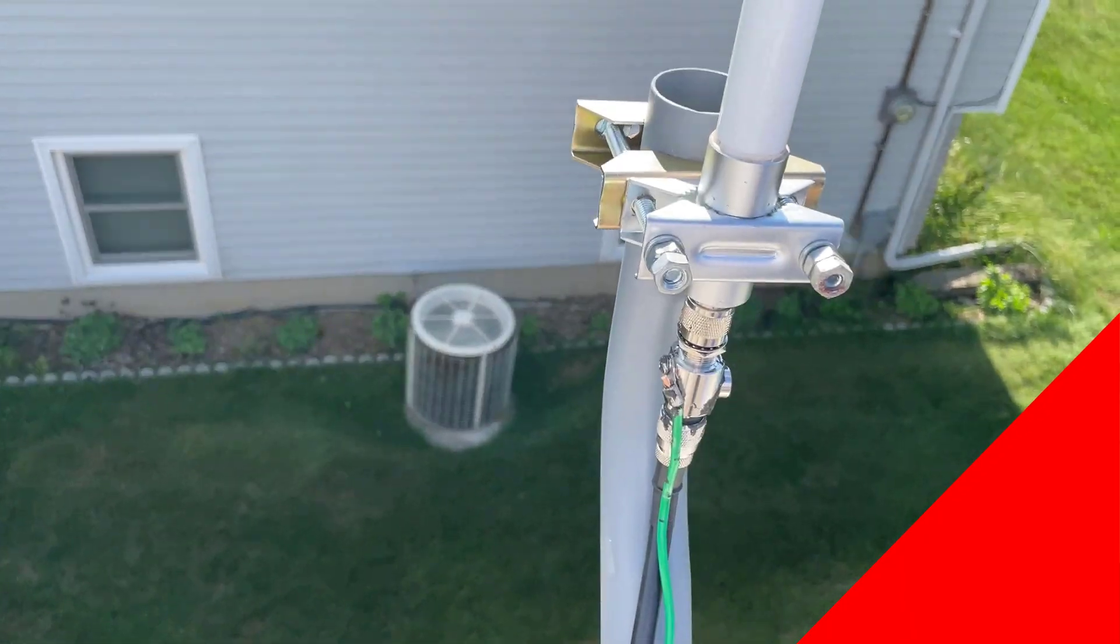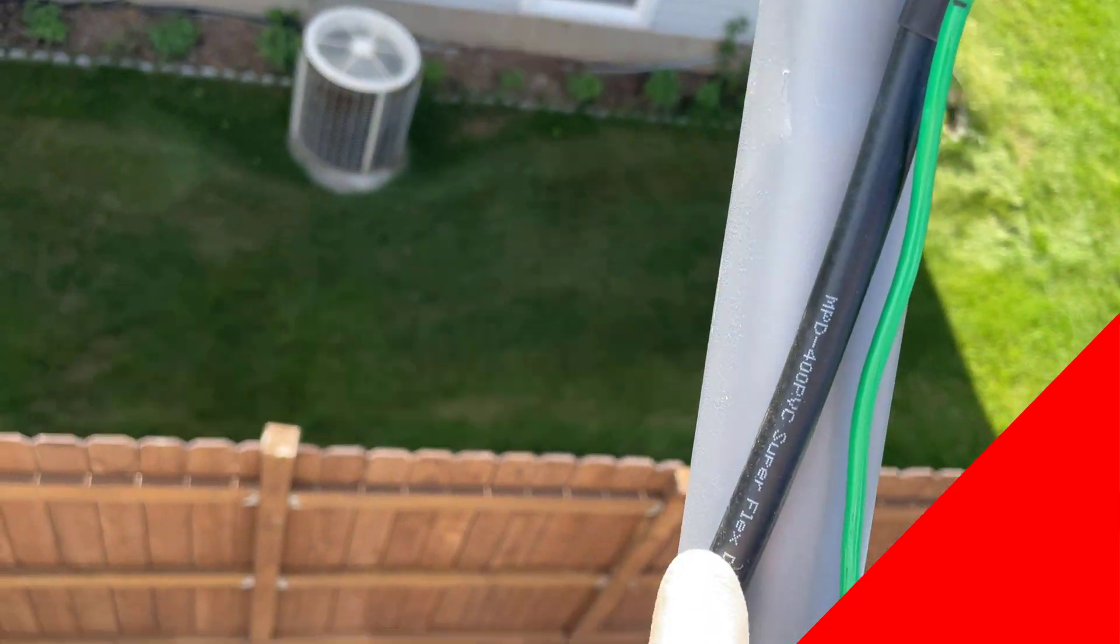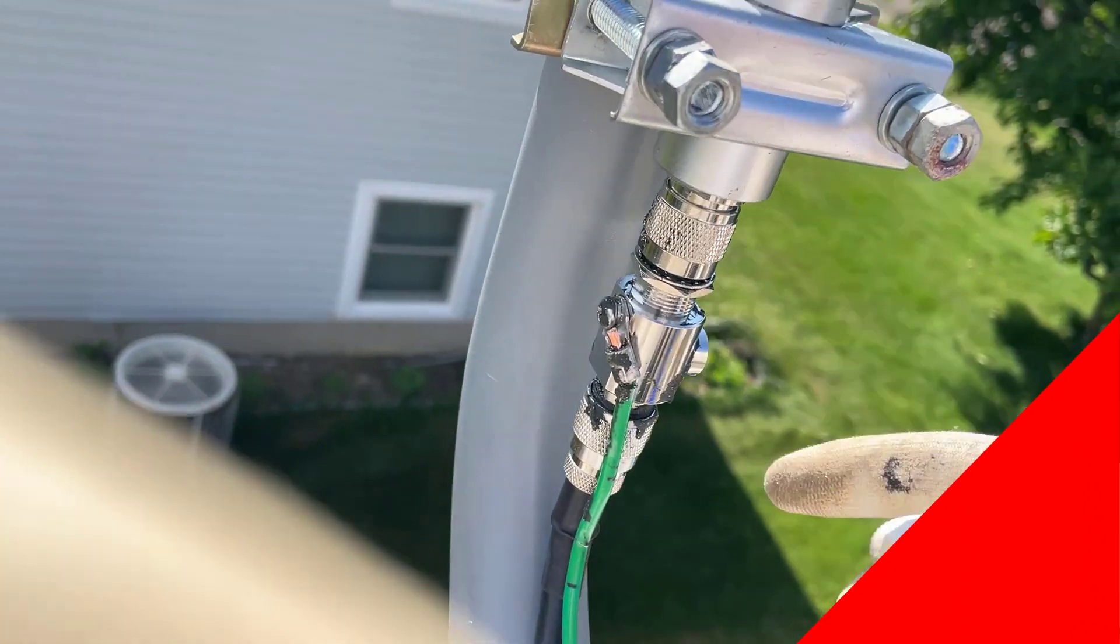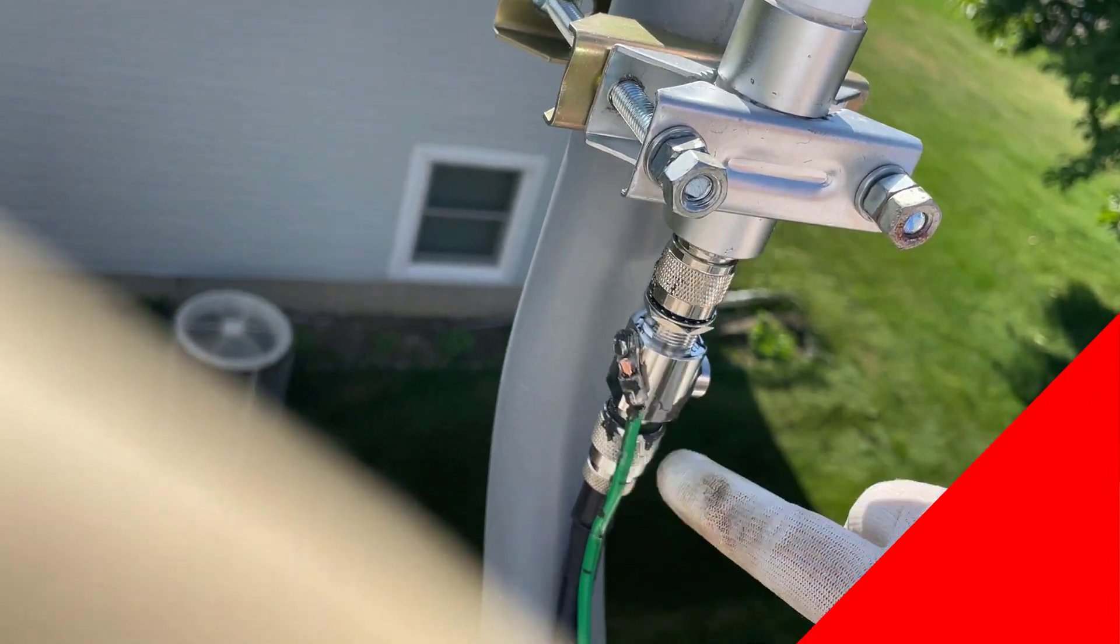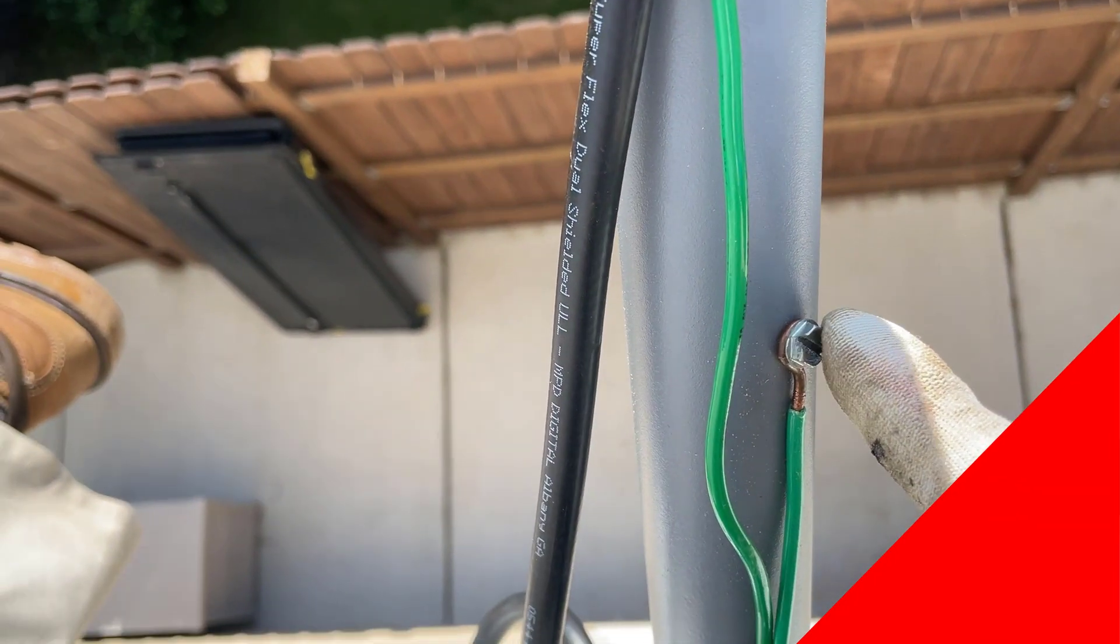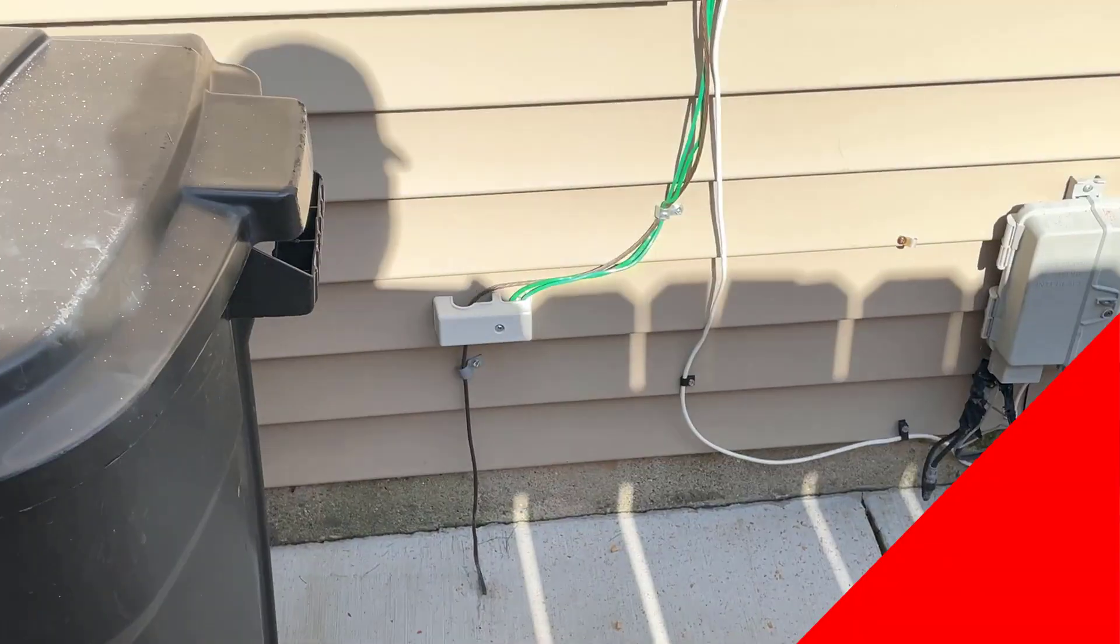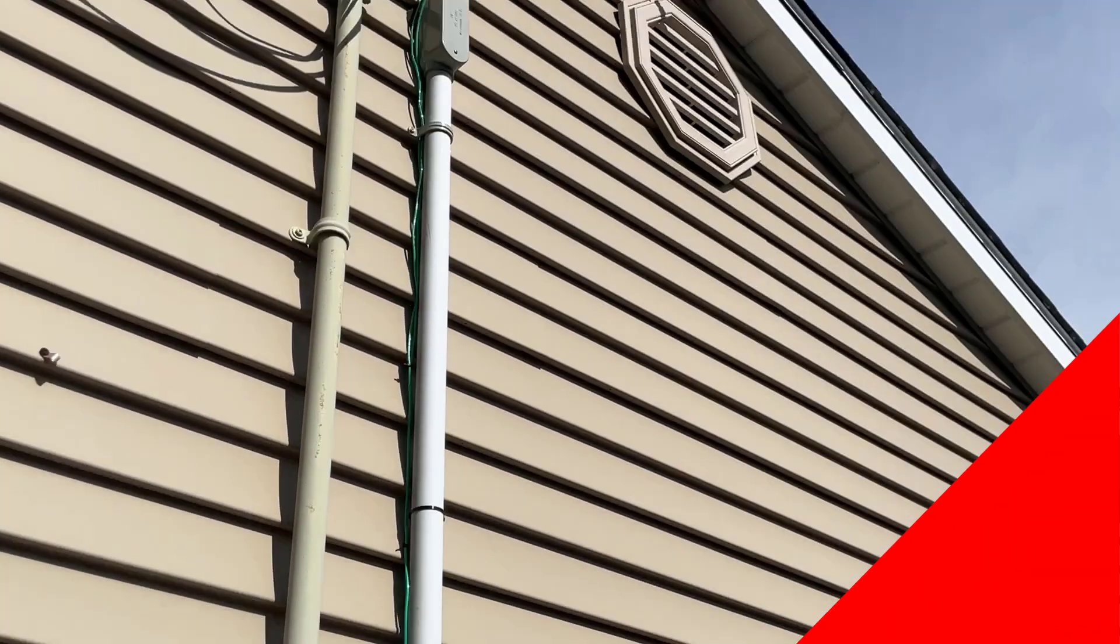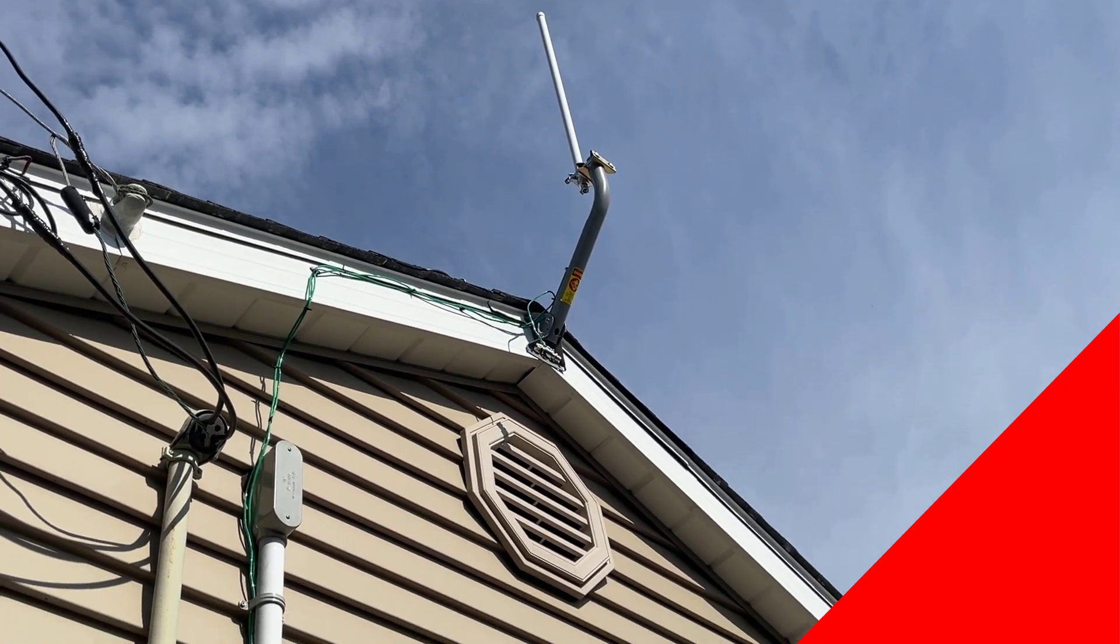Just finishing up up here. I took apart the old LMR 240 and I put in the LMR 400. I'm using the same lightning arrester that I had. I still have the ground here, and I have the ground here on the mast and the ground right here on the lightning arrester. Those are two 10 gauge wires that go all the way down to the ground at the bottom, down there to the electrical service.